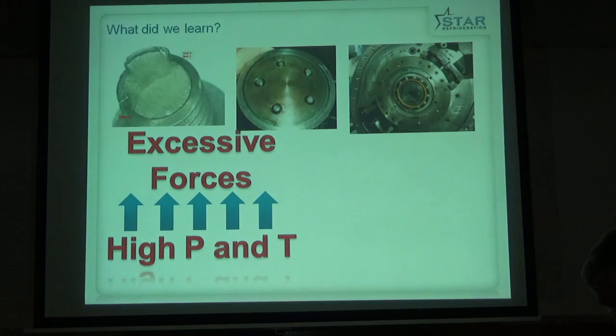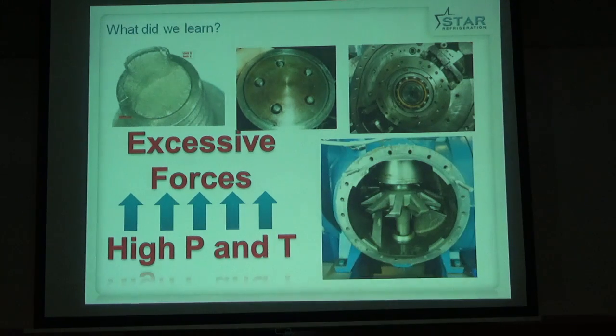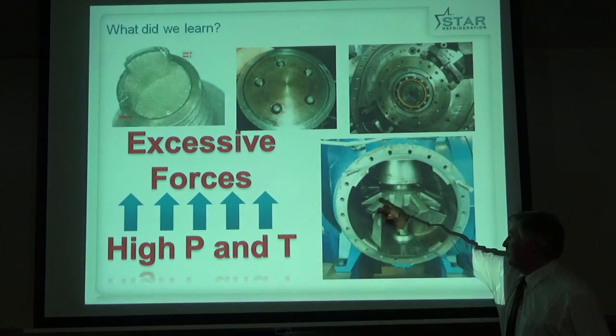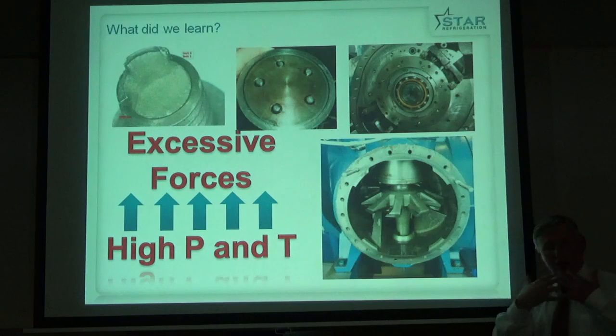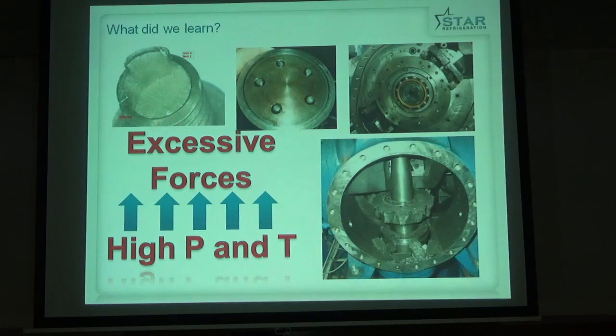So what happens to a screw compressor when you don't have a thrust bearing anymore? Well, here's a before picture. You can see all of this is a gate rotor with all the teeth which mesh with the main rotor to provide the compression of the ammonia. This is before and this is after. No teeth anymore. So that's all what comes from running at these high pressures and having to deal with the excessive forces.